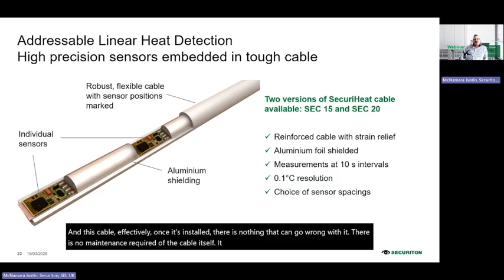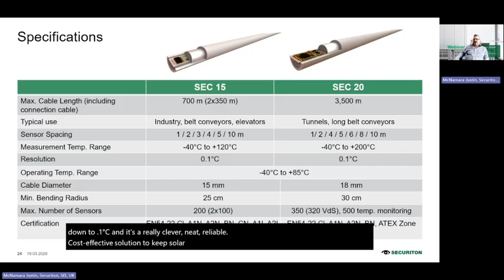Focusing on the SEC 15 cable, the maximum length we can run it is 700 meters, an awfully long distance covering a solar array on a roof. Sensor spacing allows individually addressable sensors every meter, every 2 meters, up to 10 meters, with resolution down to 0.1 degrees centigrade. It's a clever, neat, reliable, cost-effective solution to keep solar panels operating as long as the sun is shining.